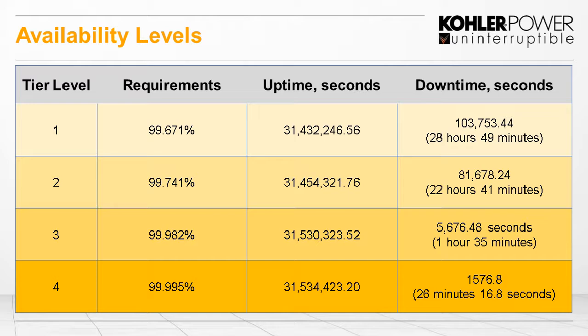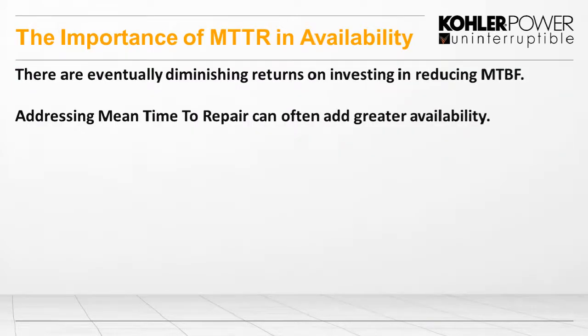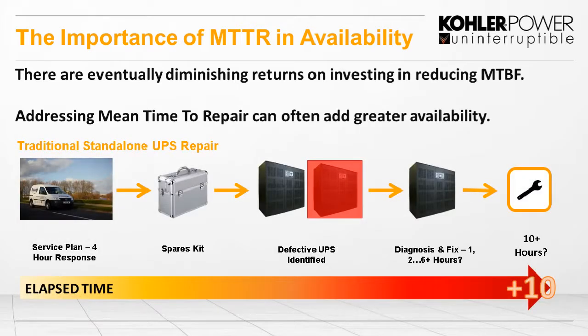And we have to look at that when we're looking at the UPS part of the data center. So what we can do is obviously make the UPSs more reliable, and the MTBF can be increased. However, if we address the mean time to repair, we can make the greatest difference to the availability of the system. So if we look at a standalone unit, for example, a mean time to repair on this means we get a fault call of the system. Customer gives us a call.